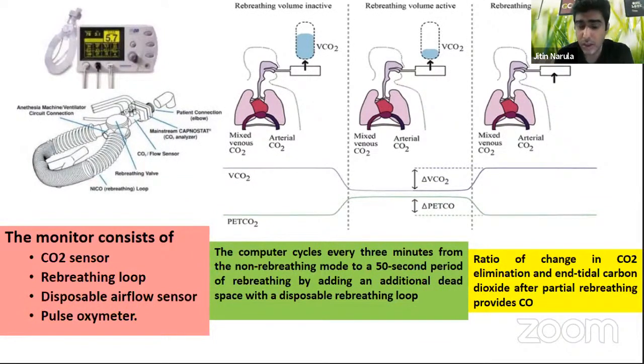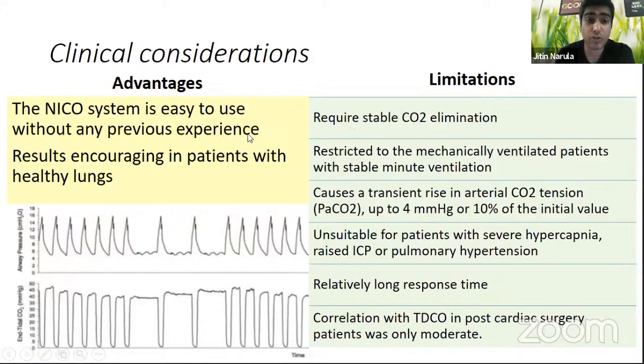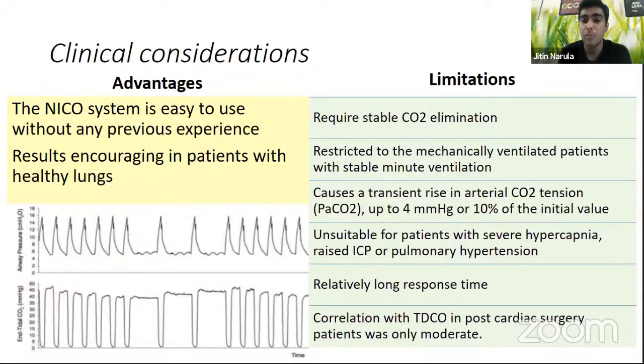The partial carbon dioxide re-breathing method applies the Fick principle. Based on alternating between re-breathing and non-re-breathing periods, the NICO monitor integrates a CO2 sensor and flow sensor measuring CO2 production from the difference between expired and inspired CO2 concentration. A correction is applied for intrapulmonary and anatomical shunt using FiO2, SpO2, and an adaptation of Nunn's hypothesis. The computer cycles every 3 minutes from non-re-breathing mode to a 50-second re-breathing period. A ratio of change in CO2 elimination and end-tidal CO2 after partial re-breathing allows cardiac output calculation. Clinical advantages: easy to use without previous experience, with encouraging results in patients with healthy lungs.